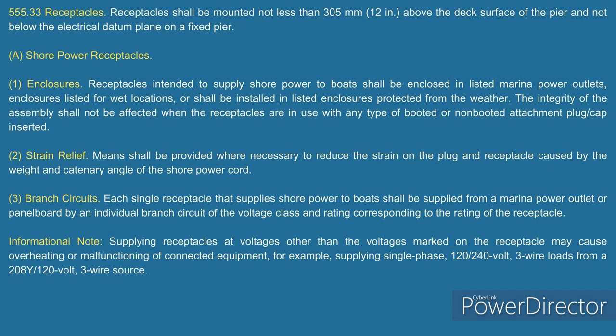Right. It's a receptacle, isn't it? Oh yeah, that's my whole point here. And then if you look at the branch circuits in Part 3, what does it say? Each single receptacle that supplies shore power to boats shall be supplied from a marina power outlet or panel board by an individual branch circuit of the voltage class and rating corresponding to the rating of the receptacle.